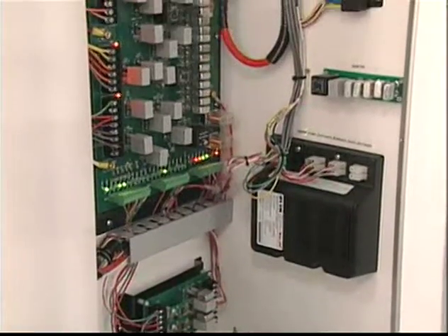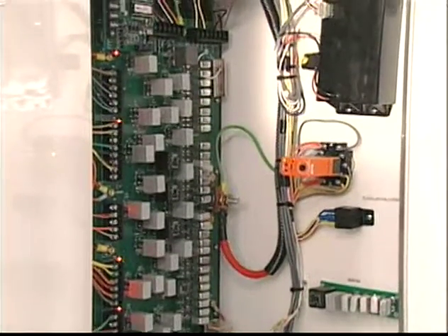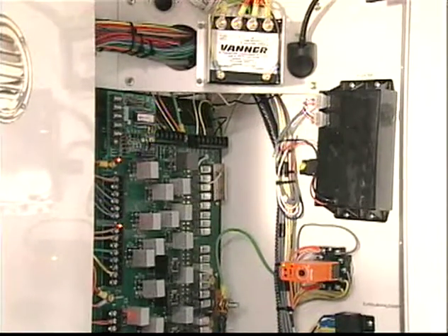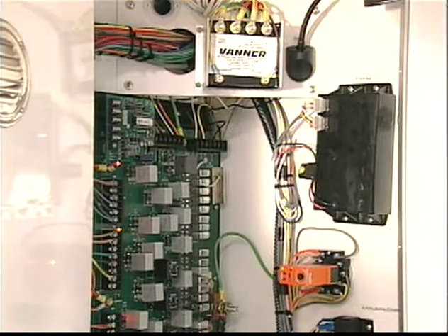Medtec's PC board has been designed for improved serviceability. All circuit breakers and relays are plug-in style and can be purchased at your local retailer. Before you remove any relay, circuit breaker, or any other electrical device from the PC board, first sketch its location and hookup for reinstallation. The green and red lights provide you with a quick check of the electrical functionality of the PC board. The green LED lights indicate you have electrical relays and circuit breakers in the PC board and are operating. Simply stated, if your green light is not energized, your problem is before the PC board. And if your red light is energized, your problem is after it leaves the PC board.